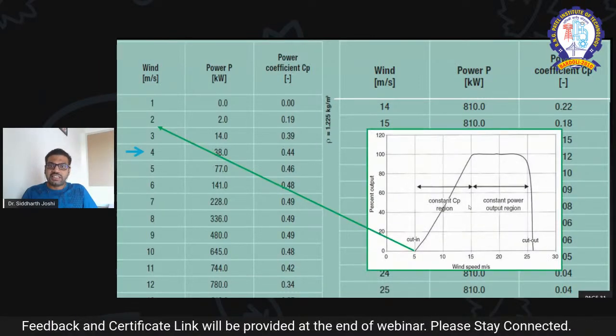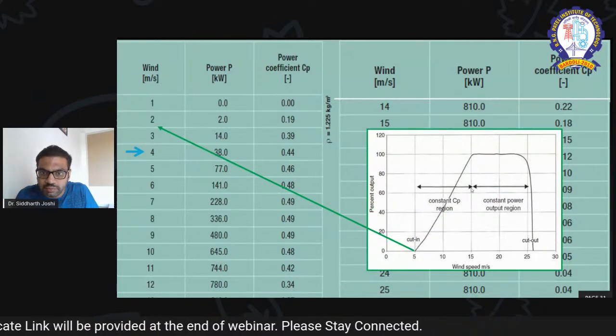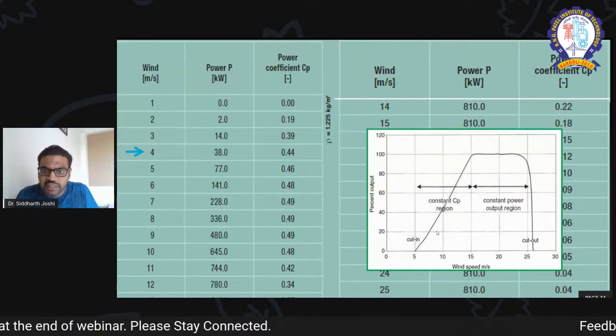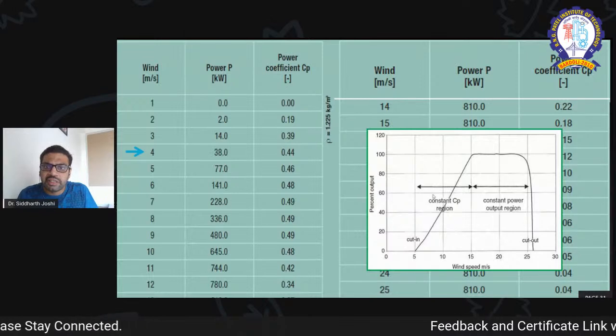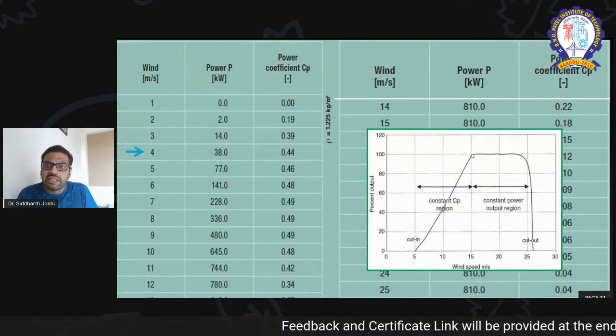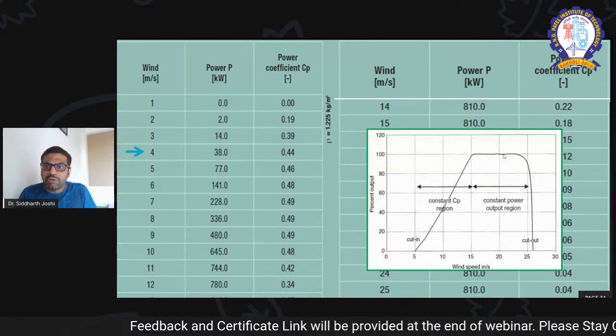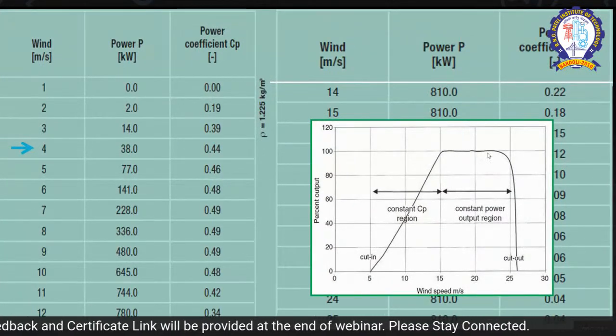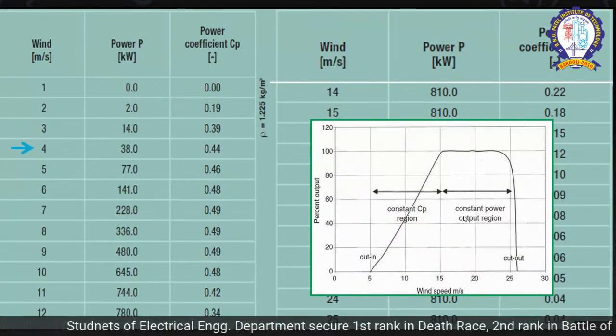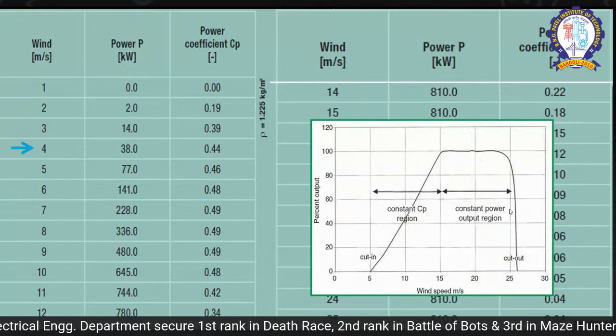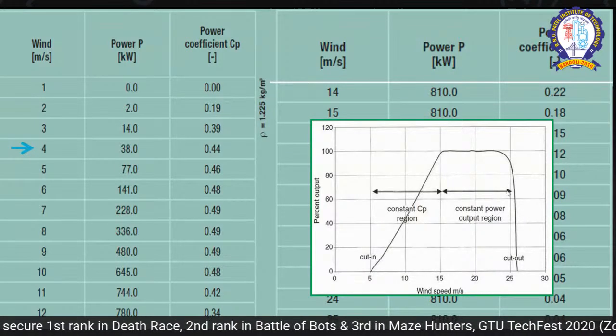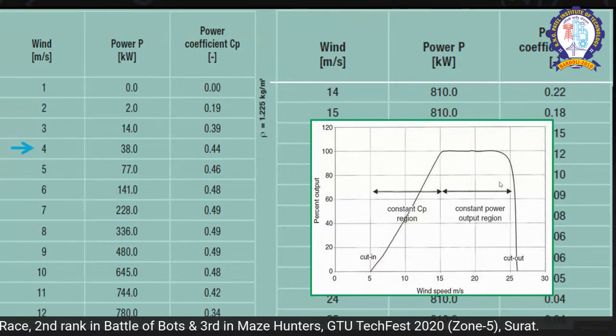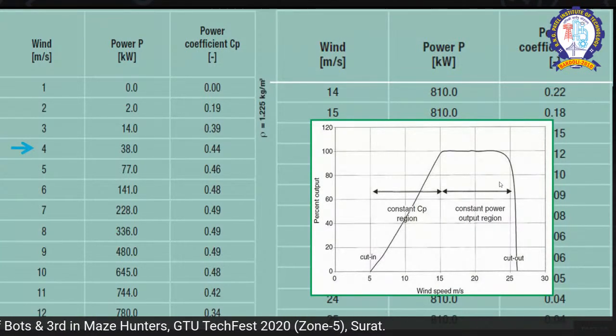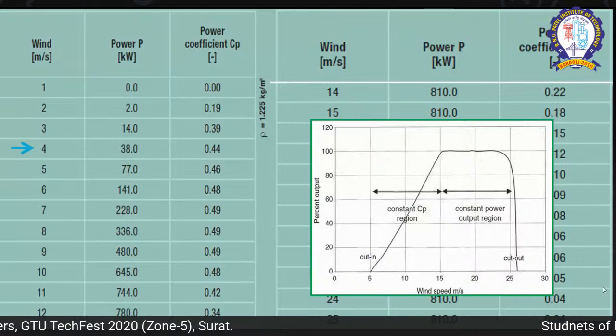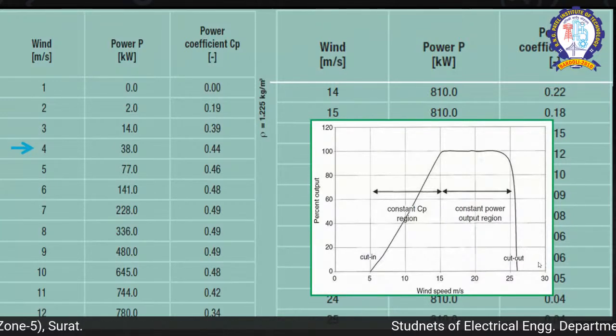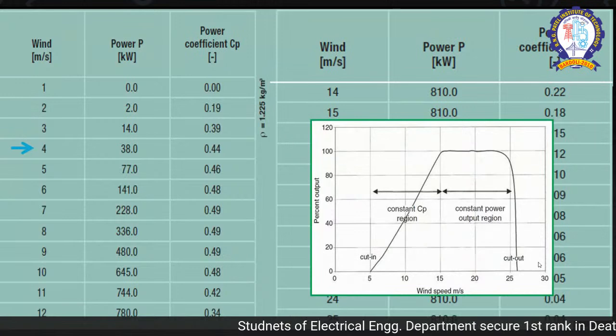Then again, if you check this characteristic, we have the cut-in speed, then we have the constant CP region. Once our power reaches one per unit, that is the rated capacity of the generator, that is the constant power output region. Again, when you reach this point, stalling, active and passive stalling, is incorporated, and then the turbine will go into the cutout range where we have the yawing mechanism.